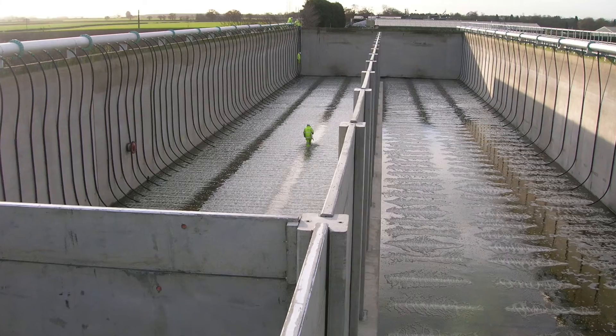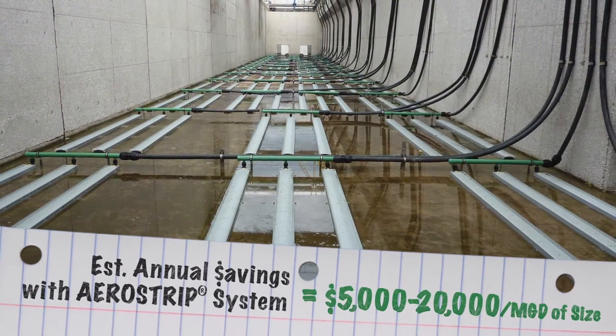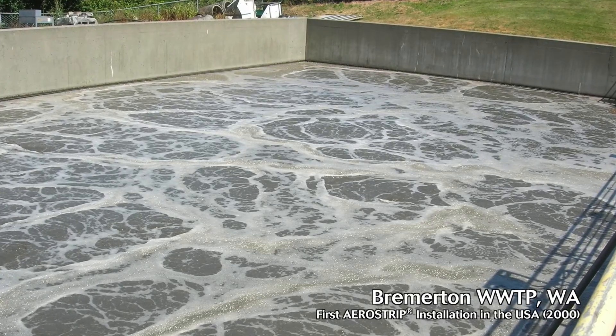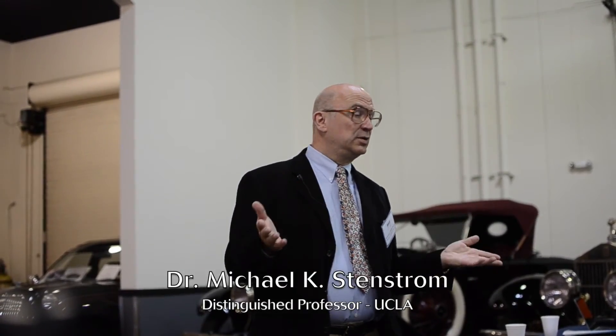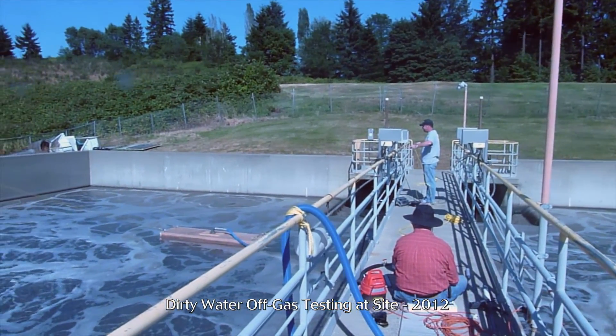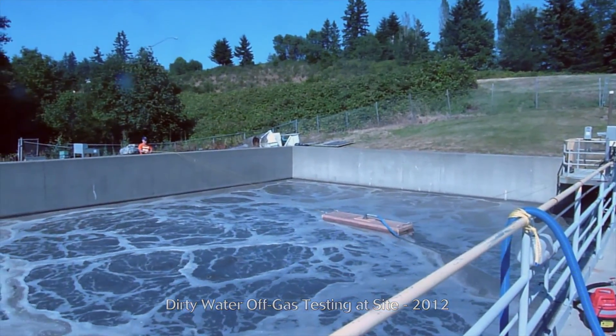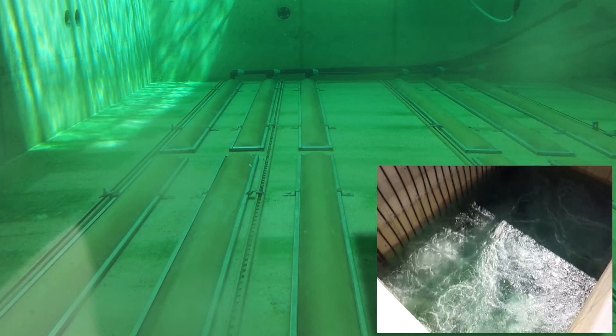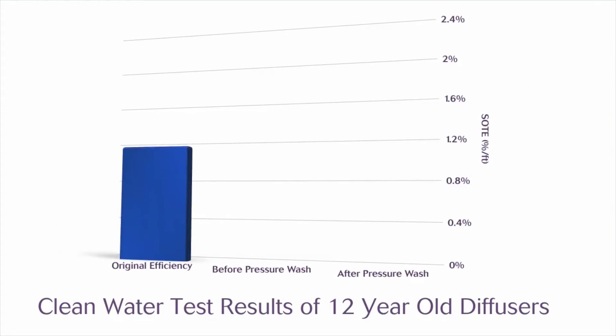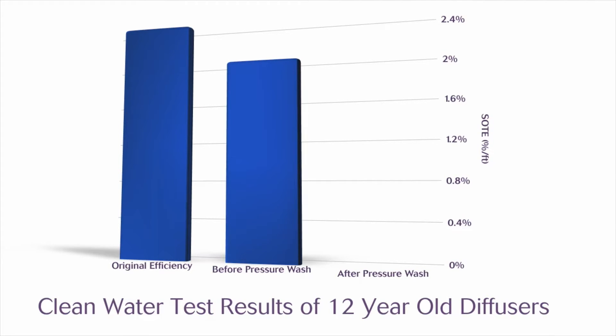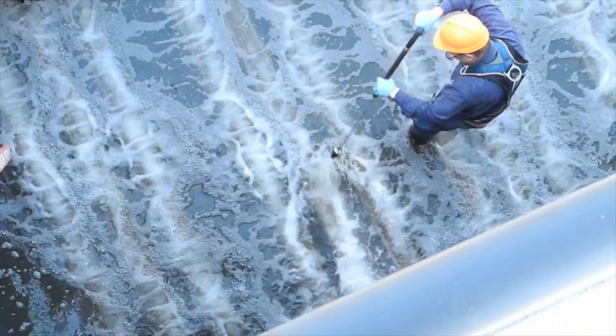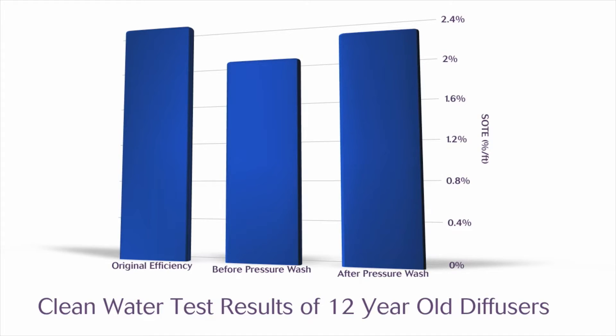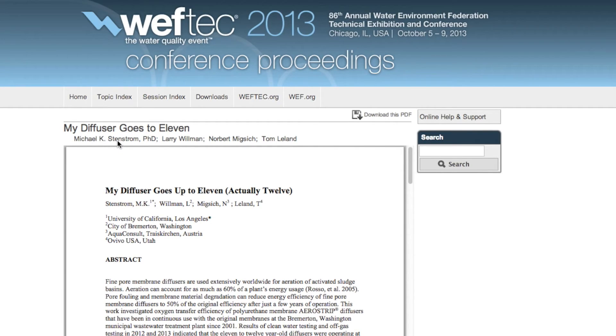In real-world terms, this can mean an annual savings to a wastewater treatment plant of between $5,000 to $20,000 per MGD of size. In 2012, these claims were put to the test when Dr. Michael Stenstrom of UCLA was invited to test 12-year-old Aerostrip diffusers, still fitted with the original membranes, at the first U.S. Aerostrip installation. Besides being the oldest fine pore diffusers he had ever tested, they were also observed to be some of the most efficient. The results indicated they were operating at 80% of the original factory-fresh efficiency. After a simple field pressure washing technique that took three to four hours, the diffusers were tested again and found to be operating at 90% of their original efficiency. His findings were presented at the 2013 WEFTEC convention in Chicago, Illinois.